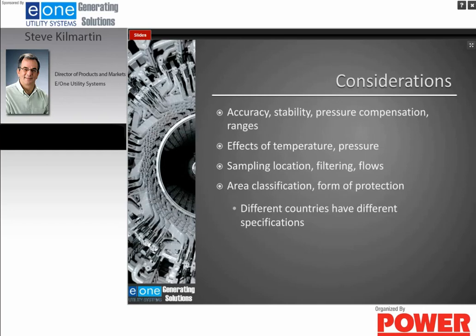You can see the considerations are similar to that of the hydrogen purity. You want it to be accurate and stable. One additional thing with dew point is you've got to make sure that the sensor you're using has pressure compensation. If the sensor is calibrated at atmosphere, when you put it in the generator, which is under pressure, you may have to compensate for that. You need to know what the effects of temperature changes are. If you have major changes in your hydrogen temperature, you want a constant pressure.